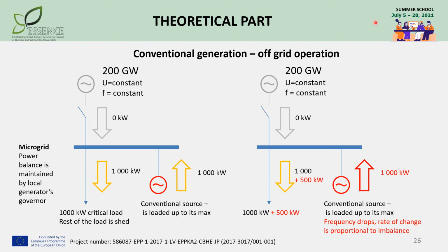The disadvantage of this case is that in case of a sudden increase of the load remaining online, the generator will not be able to compensate this imbalance, and frequency will drop with a speed proportional to the imbalance. Thus, it's necessary to match the capacity of the distributed generator and max critical load carefully at the planning stage.